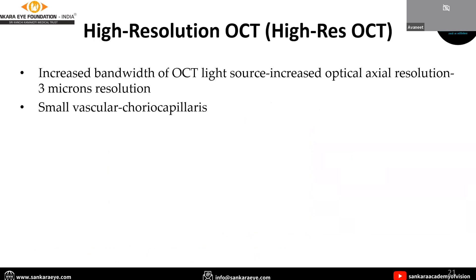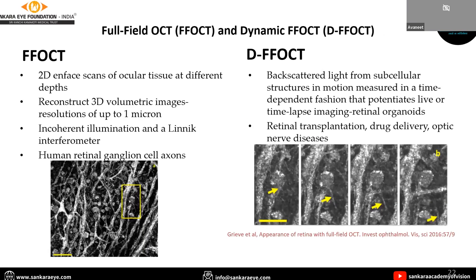The resolution of OCT can be increased by increasing the bandwidth of the OCT light source. Full field OCT forms 2D en face scans of ocular tissue at different depths and can reconstruct 3D volumetric images at resolutions up to one micron, which is especially helpful for visualizing human retinal ganglion cell axons. Dynamic OCT is a derivative of full field OCT where backscattered light from subcellular structures can be seen in motion, showing movement of axons over time.